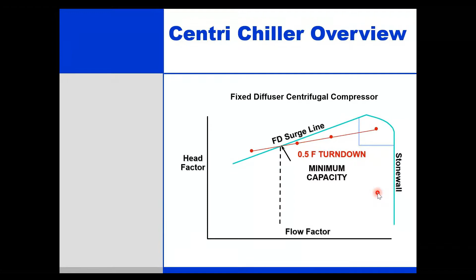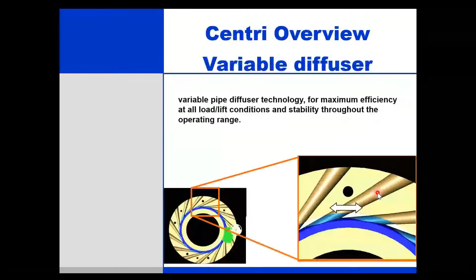Now, we have discussed over here the limitation of the centrifugal chiller, that it has a tendency at lower load to surge. To address that problem, there's a specific technology adopted by certain manufacturers, and most of them have adopted this. They deploy a technology called a variable geometry diffuser. That means whenever the operating point of the centrifugal chiller is near the surge line and there is a tendency of it touching the surge line and the compressor getting stalled, the pipe diffuser is basically pinched. That means the diffuser through which the refrigerant is flowing is pinched.